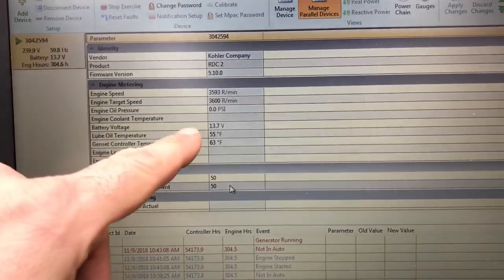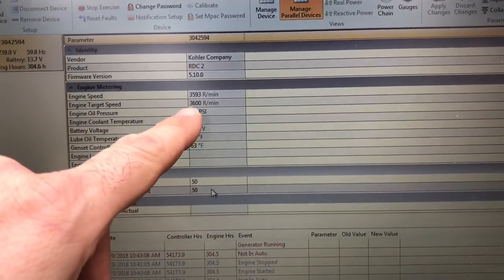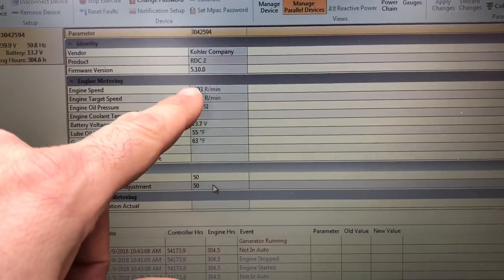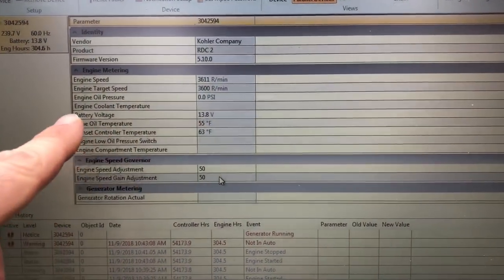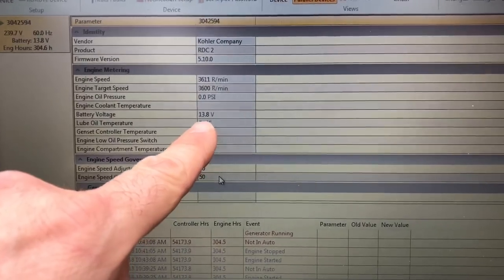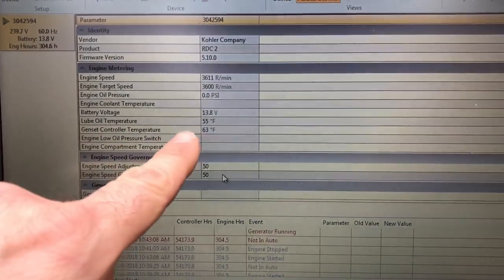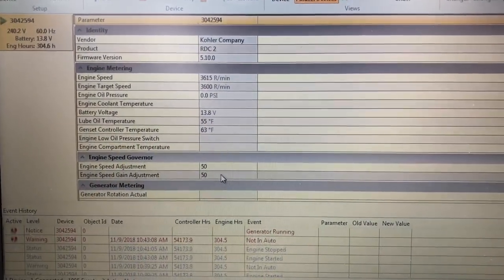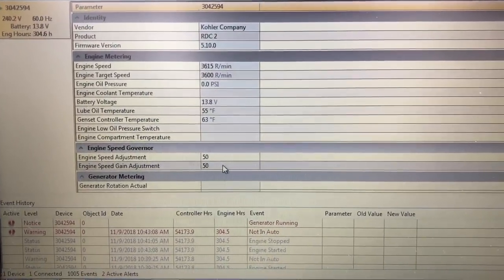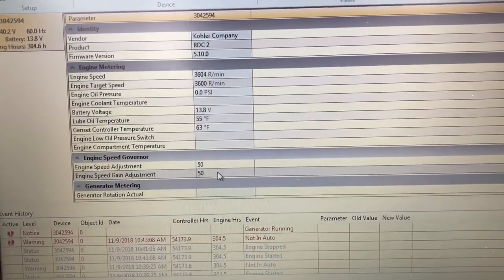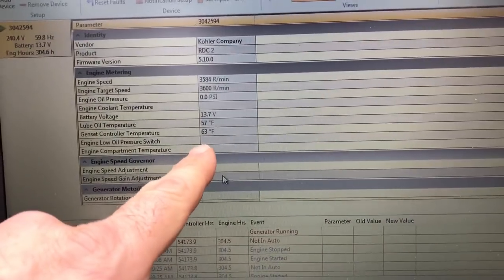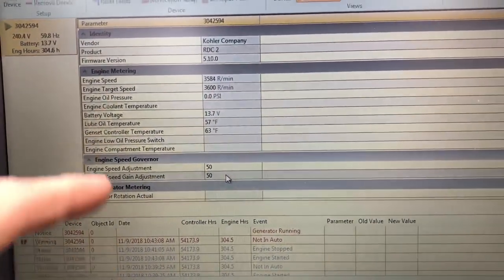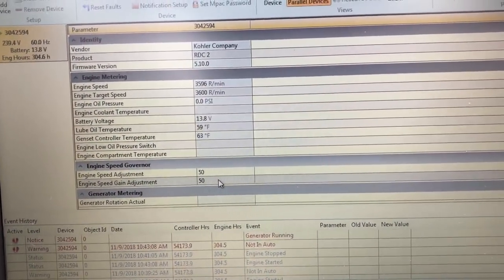Oil pressure, I can't read anything. My target speed is 3600, I'm right under but not far off. Battery voltage 13.8, my oil temp is 55, it was 37 when I started because it's 37 degrees out here right now. My genset controller temperature is 63 because it's above the engine so the engine is just warming it up a little bit.